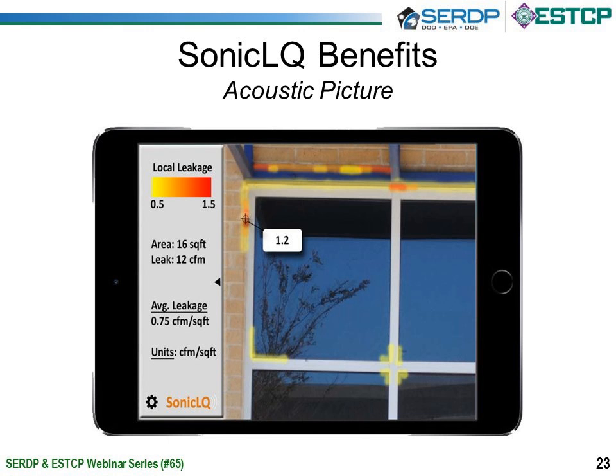I can look at the localized air leakage rate in terms of CFM per square foot. The final product is that I take acoustic and visual pictures of the outside of the building at a distance, which we will see here is about 3 feet. Those pictures will give you the overall air leakage for that entire section under test, as well as locate and size the individual leaks.